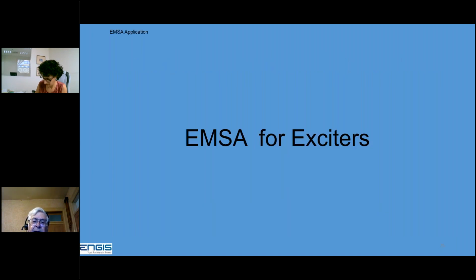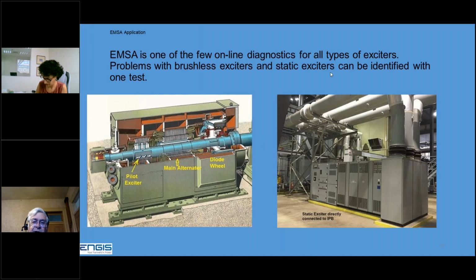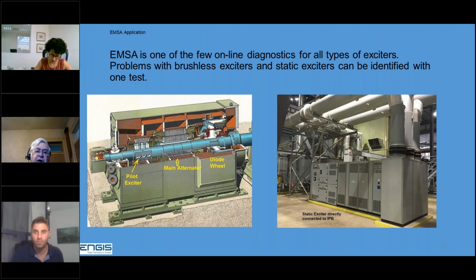One of the nice things about EMSA is it is one of the very few online diagnostics for exciters. And all types of exciters have been tested. The old DC generators, like are still found on large hydro generators, brushless exciters, alternator exciters, and static exciters. A large brushless exciter, shaft driven these days, has a pilot generator, the main alternator, a diode wheel for changing this high frequency AC into DC, and then that connects to the rotor, the field of the main generator.